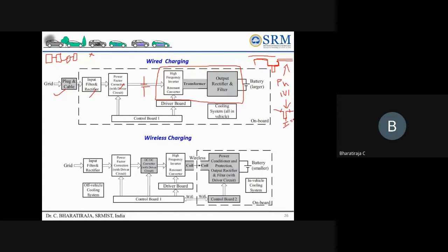But in between, what happened? In between, the DC is converted to AC, high frequency AC - converted to the kilohertz level. So you are using a resonant converter, and we are using a pulsating transformer to isolate the converter side and the inverter side, because this is the inverter side, this is the converter side.